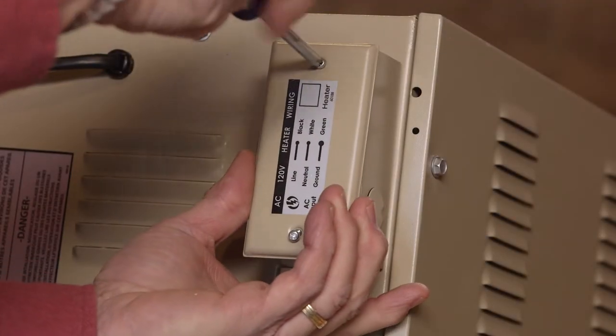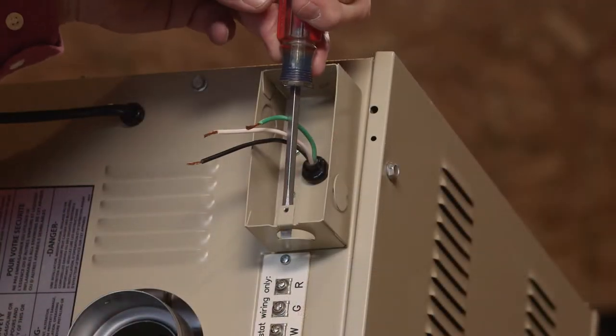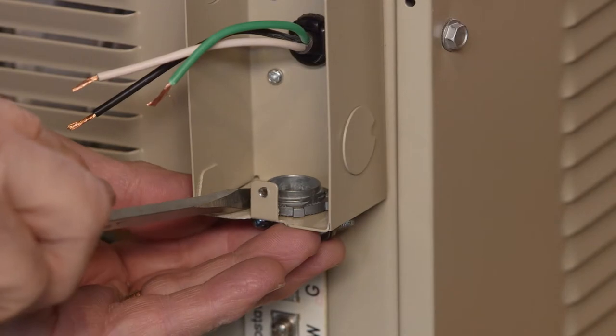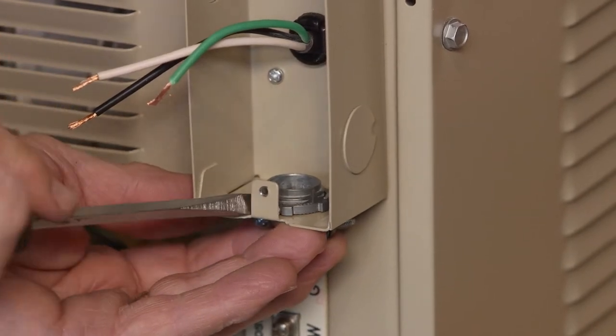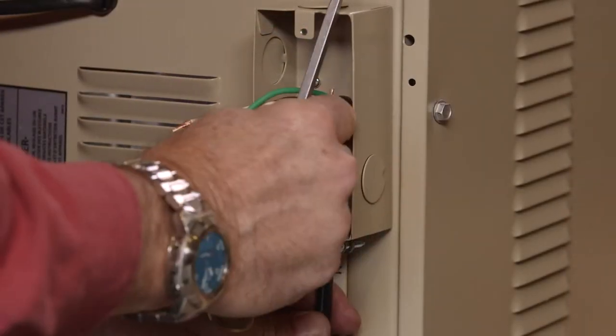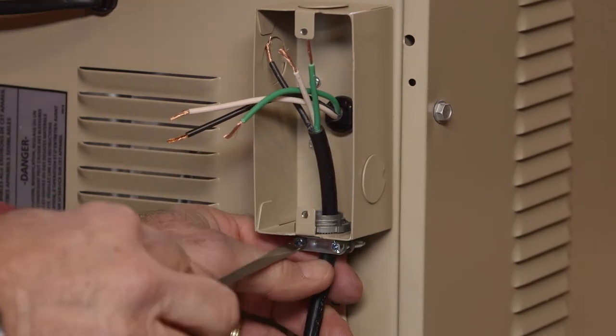You'll need a 3-wire, 110-volt AC electrical supply, a hot, a neutral, and a ground, for proper operation, connected at the back of the heater in the single-gang junction box.